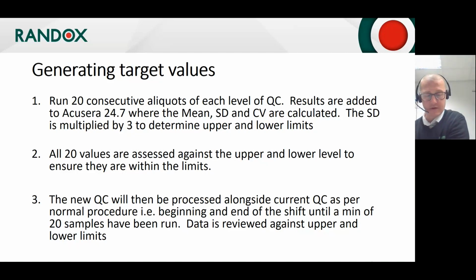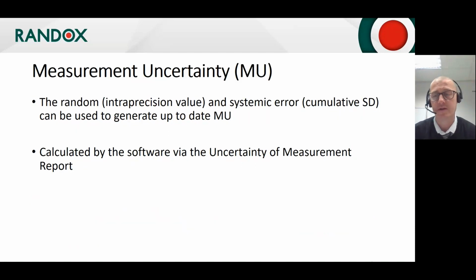The random and systemic error is then manipulated and generates your measurement of uncertainty, which ISO is quite keen on. So you need both sets of error in order to generate your measurement of uncertainty. The systemic error is basically a cumulative SD. Each time you're running your QC, it's recalculating the SD, the mean, and the CV, and it's this recalculation of the cumulative SD that identifies your systemic error, whereas your initial 20 values show your random error.